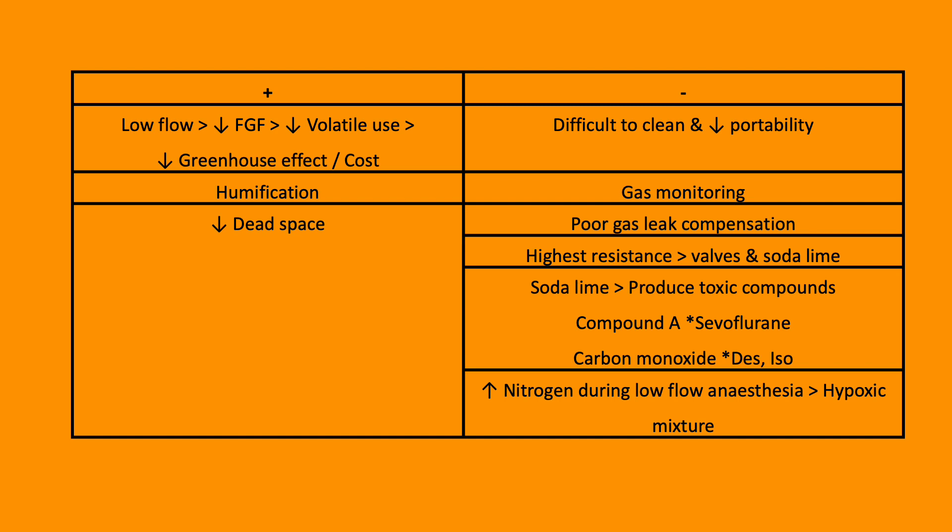Nitrogen concentrations can build up in the presence of low-flow anaesthesia, which risks the delivery of hypoxic gas mixture to the patient.